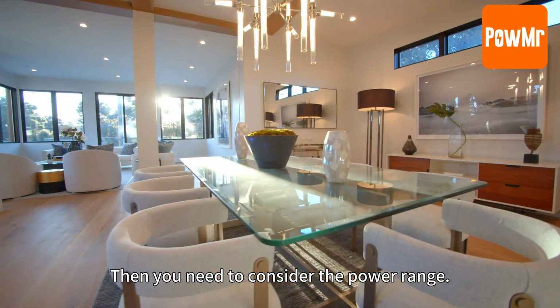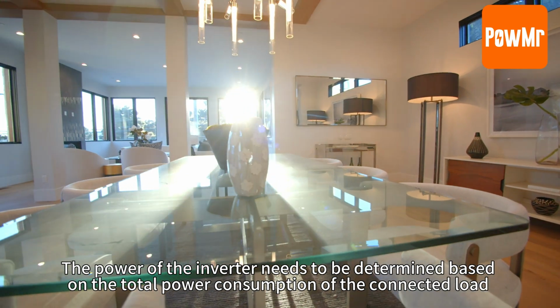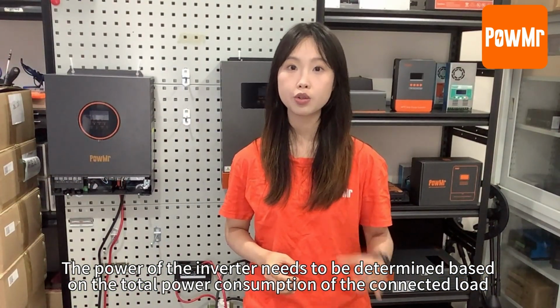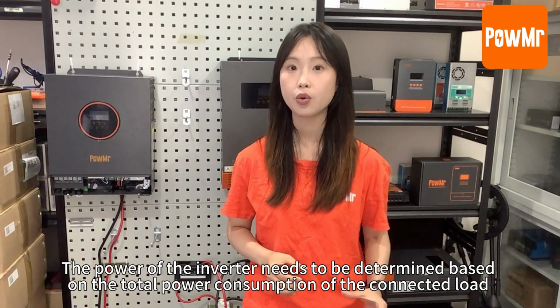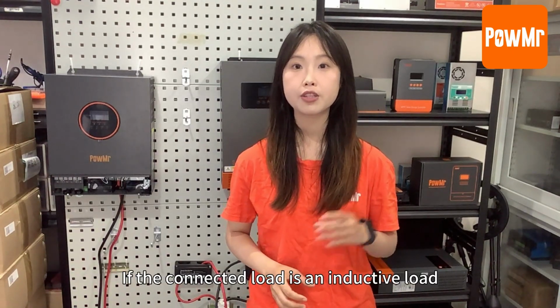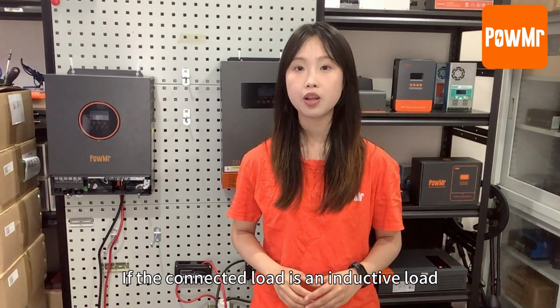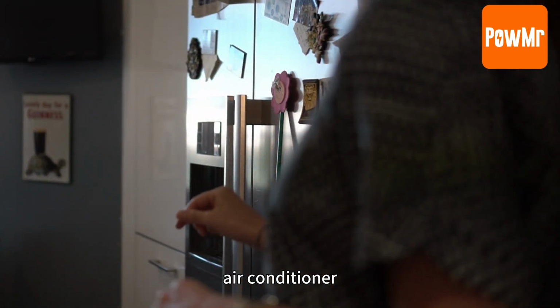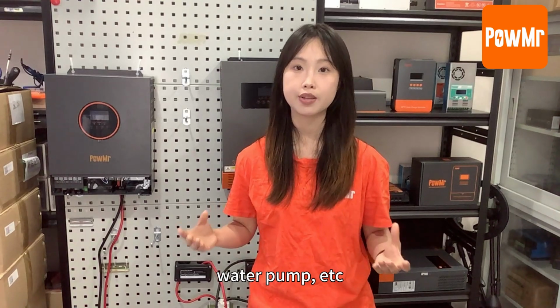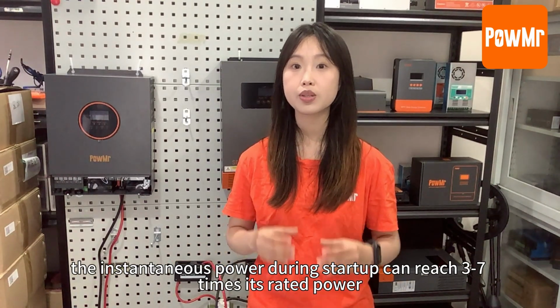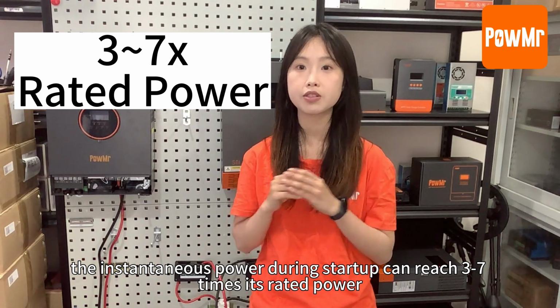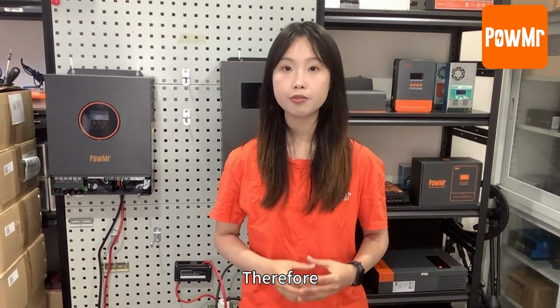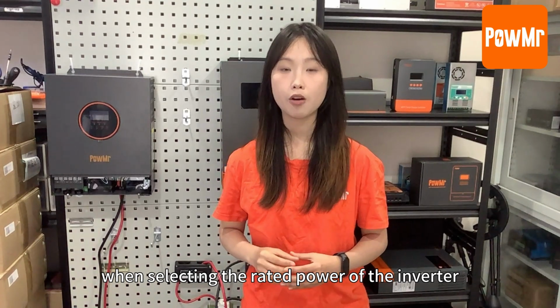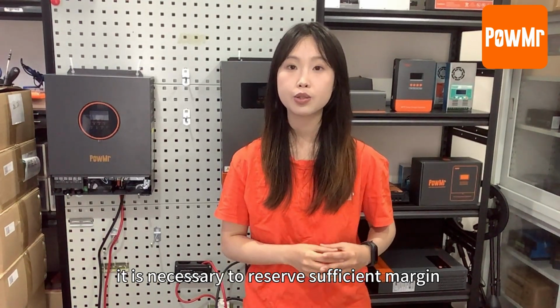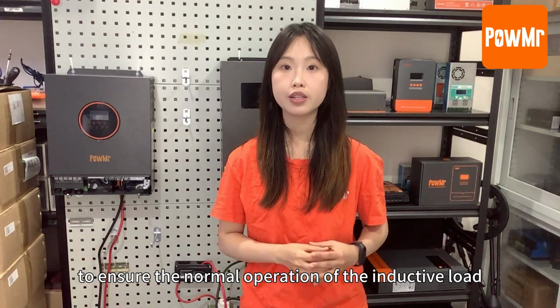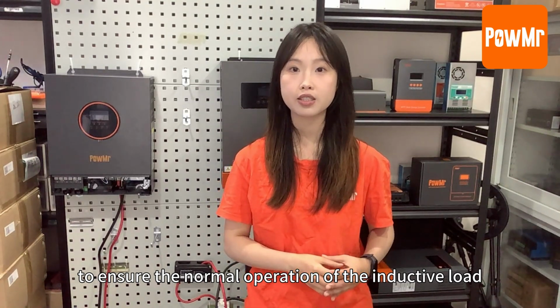Then you need to consider the power range. The power of the inverter needs to be determined based on the total power consumption of the connected load and the type of the load. If the connected load is an inductive load, such as refrigerators, air conditioners, water pumps, etc., the instantaneous power during startup can reach 3 to 7 times its rated power. Therefore, when selecting the rated power of the inverter, it is necessary to reserve sufficient margin to ensure the normal operation of the inductive load.